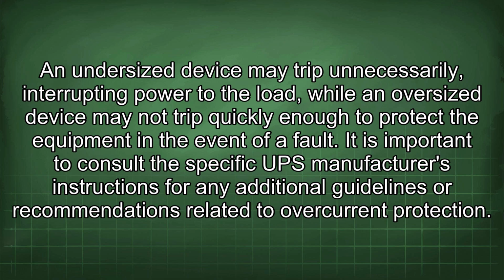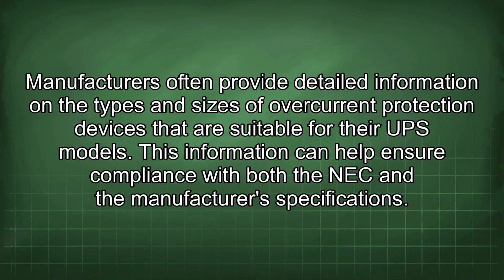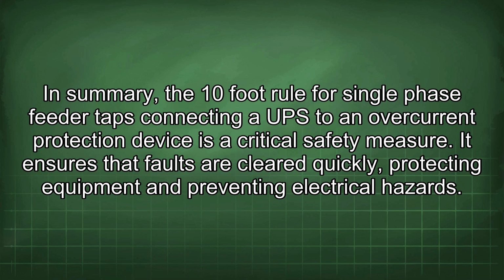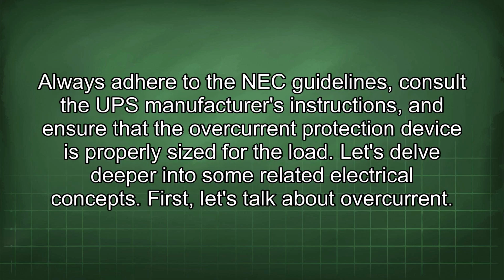It is important to consult the specific UPS manufacturer's instructions for any additional guidelines or recommendations related to overcurrent protection. Manufacturers often provide detailed information on the types and sizes of overcurrent protection devices that are suitable for the UPS models. This information can help ensure compliance with both the NEC and the manufacturer's specifications. In summary, the 10-foot rule for single-phase feeder taps connecting a UPS to an overcurrent protection device is a critical safety measure. It ensures that faults are cleared quickly, protecting equipment and preventing electrical hazards. Always adhere to the NEC guidelines, consult the UPS manufacturer's instructions, and ensure that the overcurrent protection device is properly sized for the load. Let's delve deeper into some related electrical concepts.